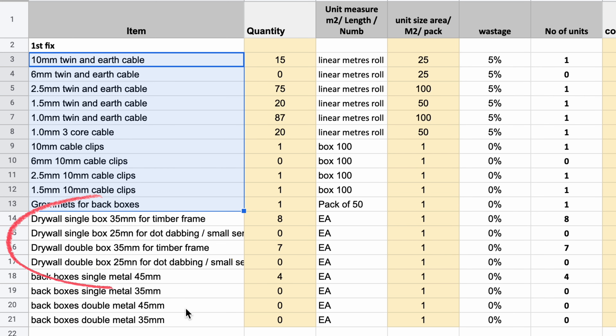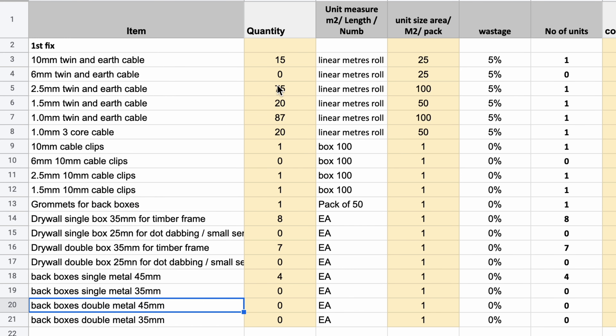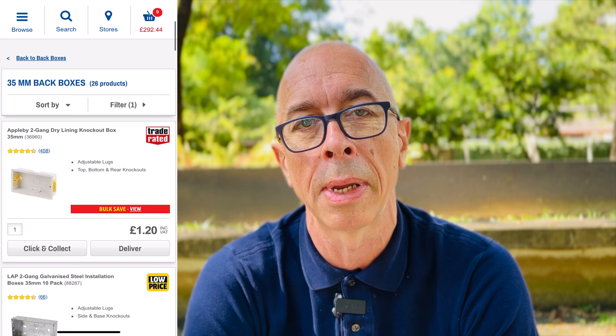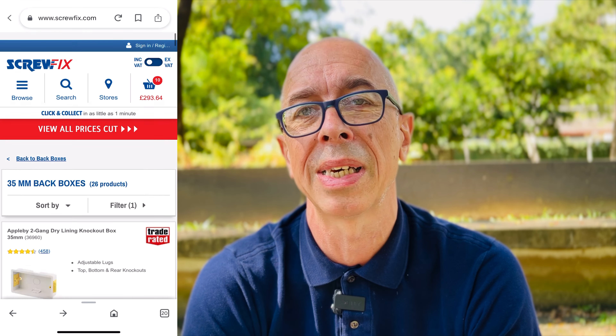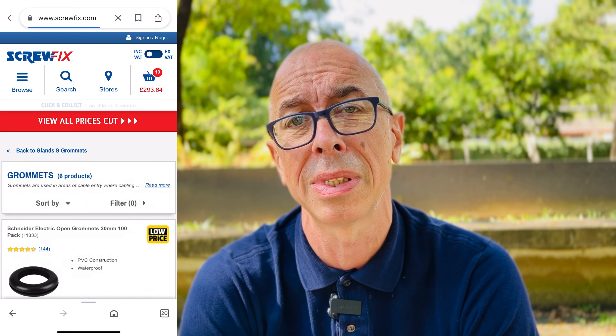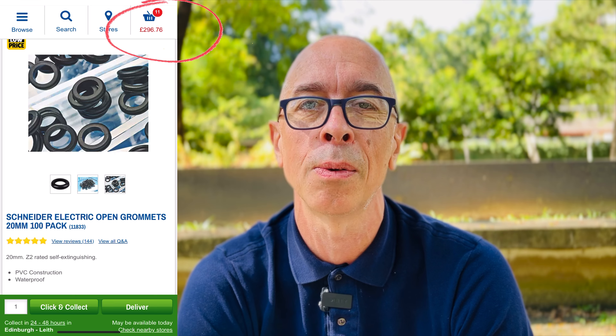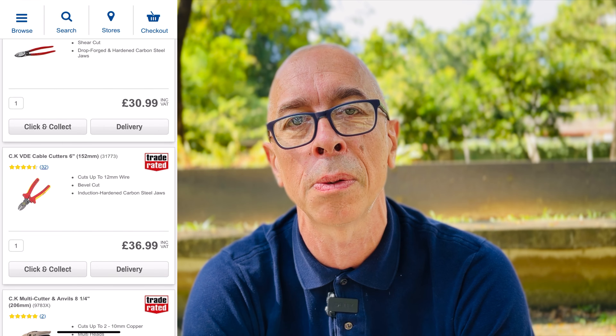For the induction and cooker sockets I'll buy deep 45mm metal back boxes to take account of the thick cable which needs more space. I'll use drywall boxes for the rest of the sockets, and I'll buy some rubber grommets to protect the cable as it passes through the metal back box. A couple of tools, some cable snips and a hammer for the cable clips — that's my shopping list for my first fix electrics. It's a relatively small amount in the scheme of costs for your build projects.